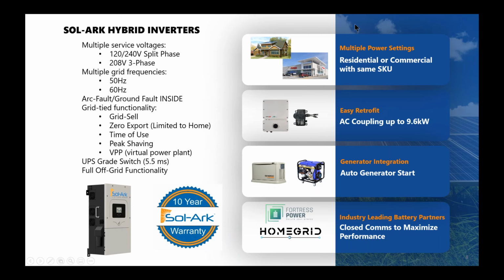We also are very easy to retrofit. One of the other features of our inverter is that it can DC couple and AC couple. Real quick explanation of what those are: if you install a Sol-Ark new, put a solar system on the house, and run the PV wires down into the Sol-Ark, that's called DC coupling. You still have direct current coming off the solar panels, so there's nothing between the panels and the Sol-Ark - the wires just come in and you have DC power. That's what we call DC coupling.